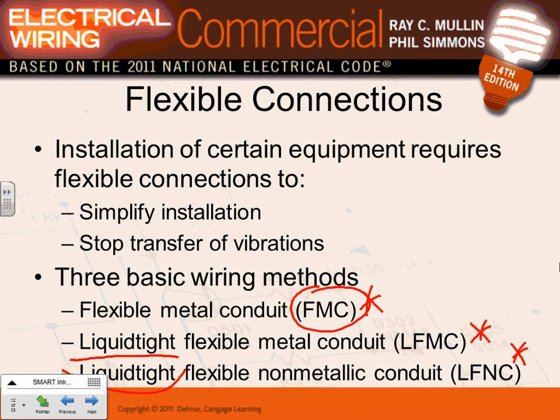What is the ideal application for flexible metallic conduit? These conduits are meant to tie to equipment. You tie to fixtures with it - air handling units, rooftop units, pumps. Why don't you want to bring EMT directly into an air handling unit? Vibration. We use flexible metallic conduit to tie to equipment for ease of installation and absorption of vibration from that equipment.